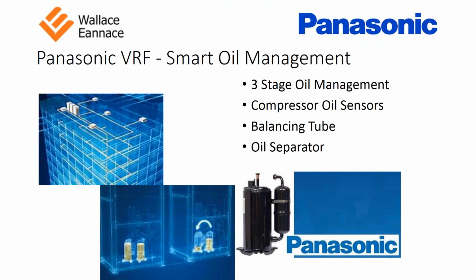Okay, Panasonic VRF smart oil management. So what is this? Panasonic, different or separate from the other VRF manufacturers, puts a lot of emphasis on oil management. In any heat pump or air conditioning system, it's essential to return oil to the compressor, that the oil is in the system for velocity to help the refrigerant travel through the refrigerant line, the piping circuit. So this is very important. If we're not returning oil to the compressor, we're doing damage to the compressor, because the compressor needs oil in order to function properly.